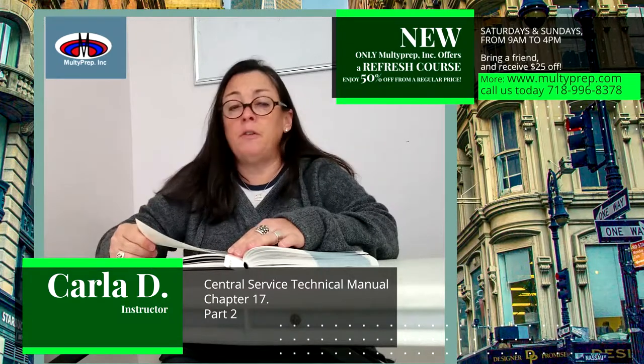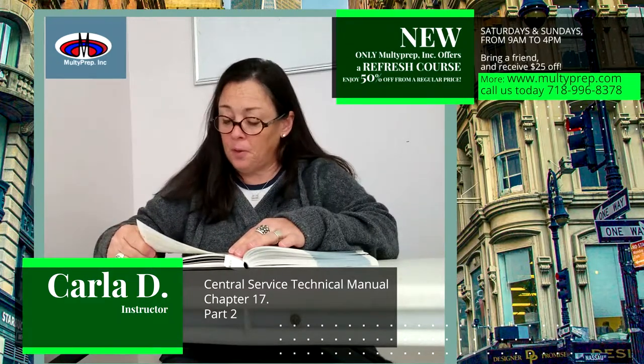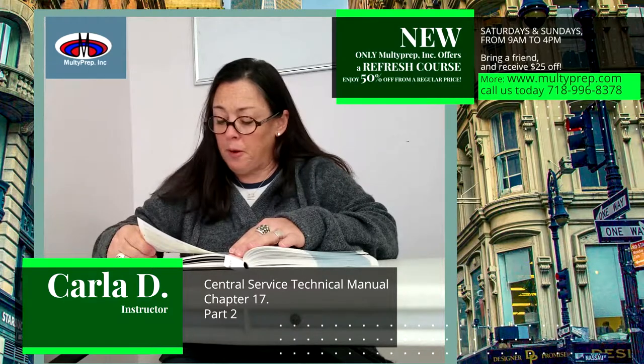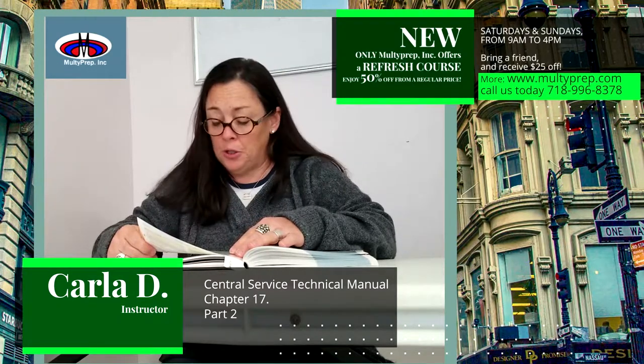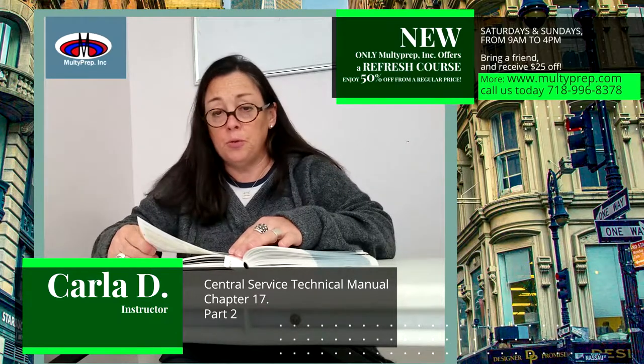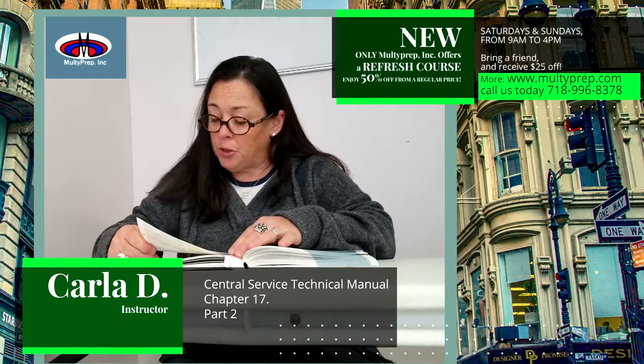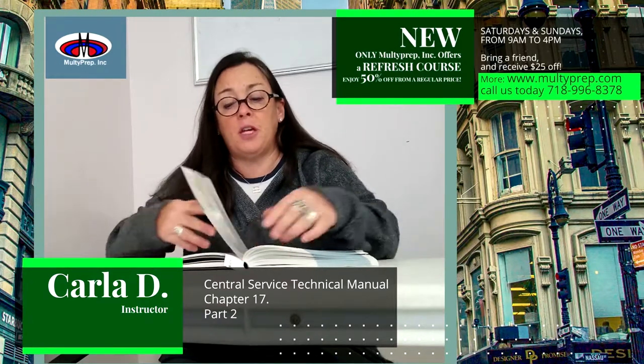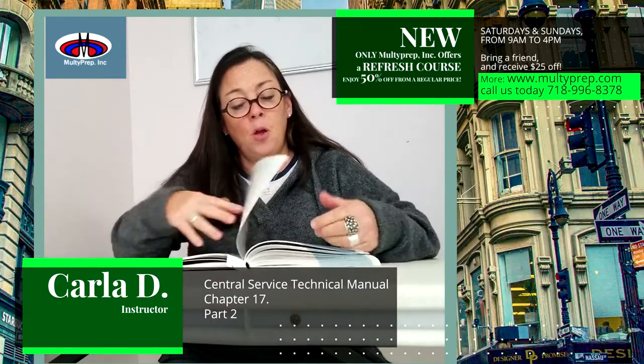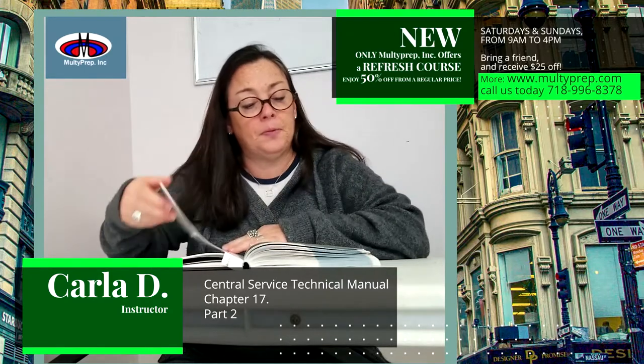Sterilizer qualification verification testing. Qualification testing is performed to verify that the sterilizer is in good working condition in the location in which it is being used. This testing also ensures that the sterilizer performs to manufacturer specifications. Qualification testing is performed after sterilizer installation, relocation, malfunctions, major repairs, or any time there is a significant change to the utilities connected to the sterilizer. A major repair is considered outside the scope of normal repairs.